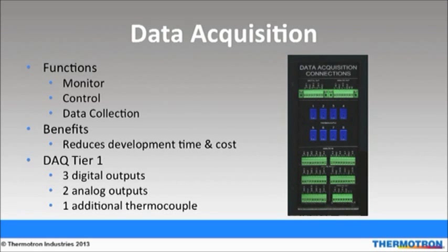It's important to track what is happening to the product under test. Thermotron's data acquisition system is configured for use with the chamber's control system, greatly increasing the chamber's capabilities and value by including product activation and monitoring to programmed or manual profiles. Users can also view product inputs, outputs, and temperatures on the same graph as other chamber conditions and profiles. With pluggable screw terminal connections for outputs, standard jacks, and additional included thermocouples for temperature monitoring, the DAQ panel is quick and easy to set up.